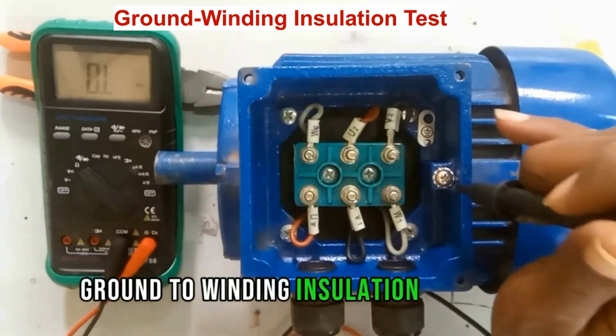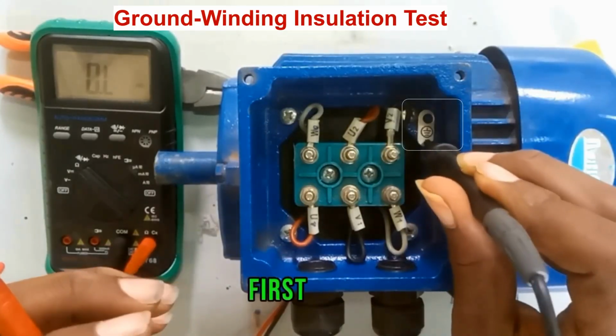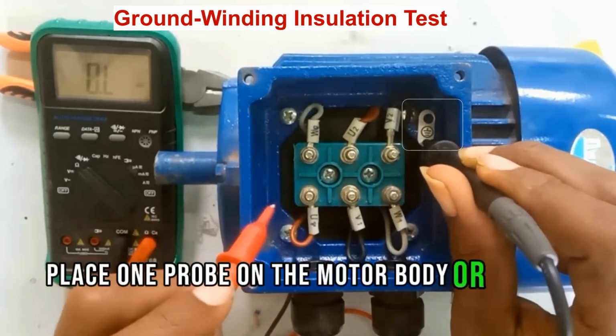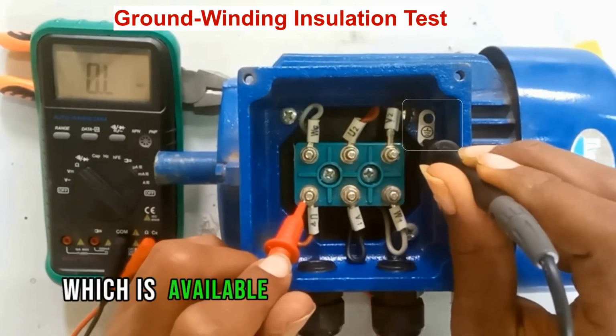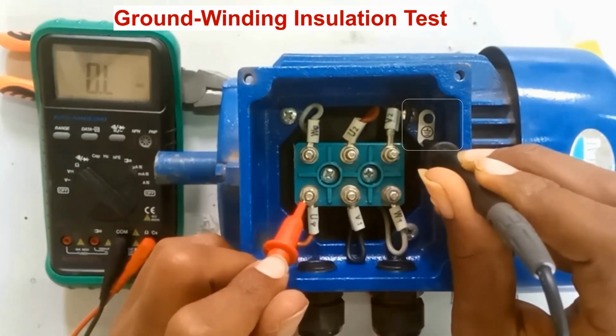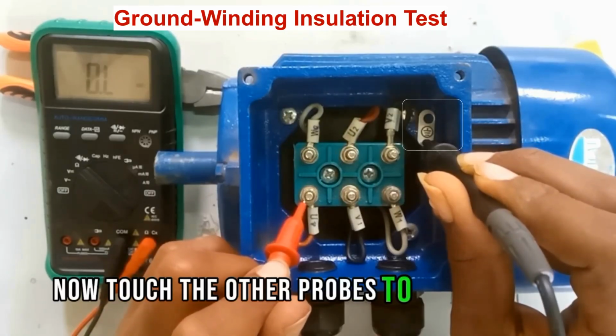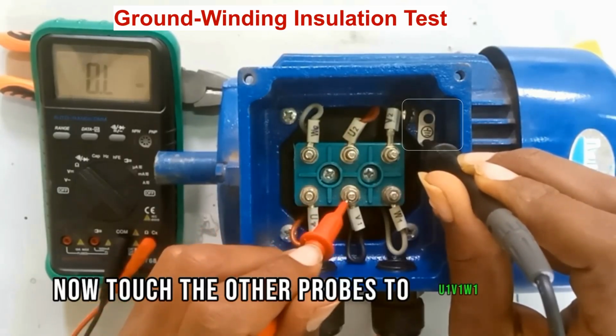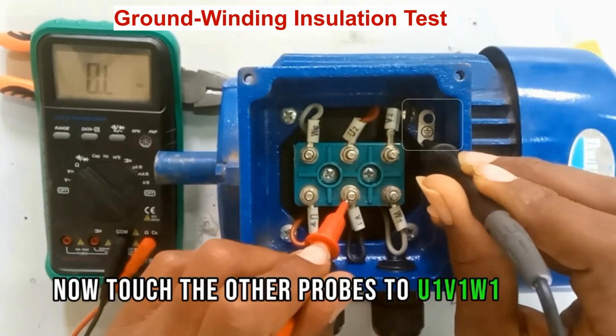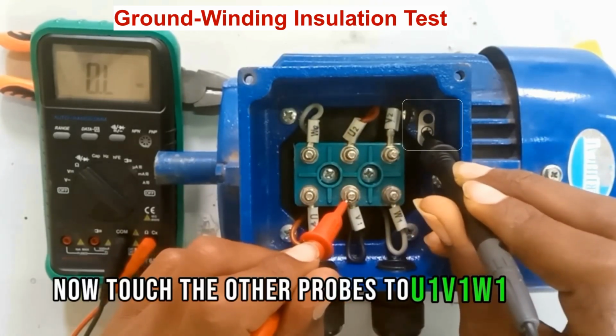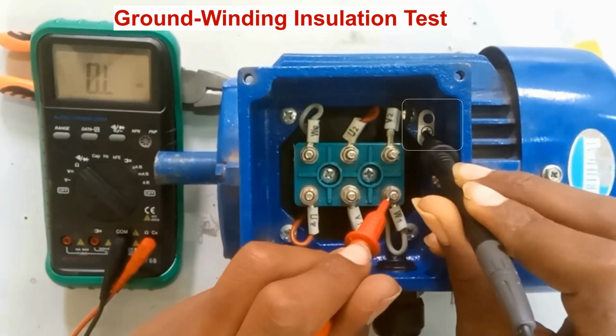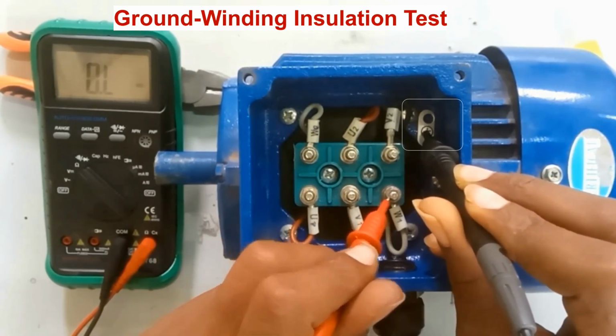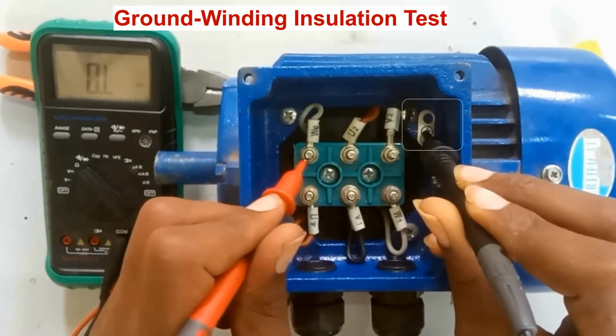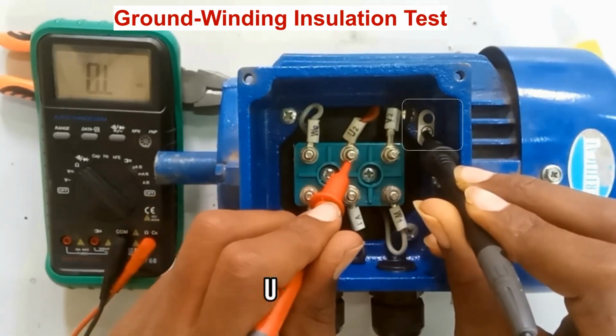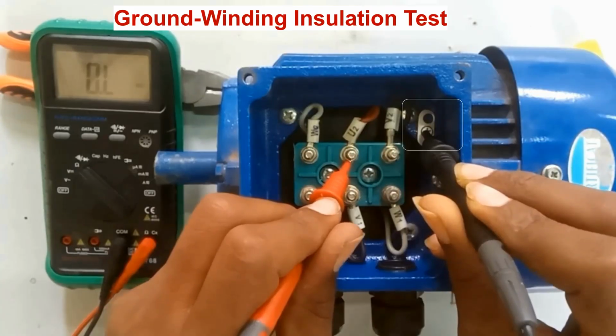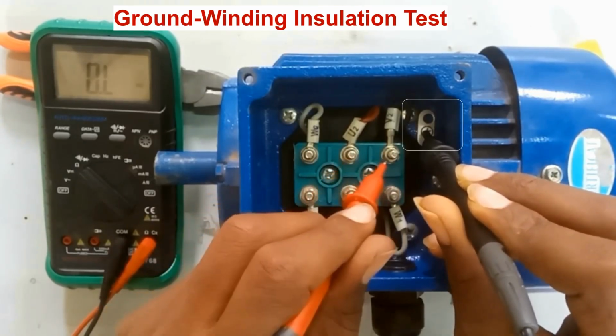Ground to winding insulation test. First, place one probe on the motor body or a ground symbol which is available on the motor body. Now touch the other probe to U1, V1, W1, and W2, U2, V2.